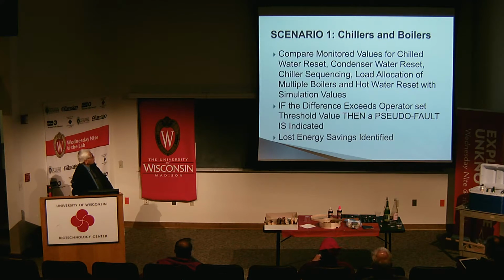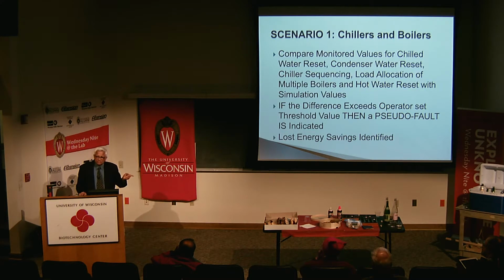Now, chillers and boilers. In this case, the monitored values for chilled water reset, condenser water reset, hot water reset, they are not optimal when you compare with simulation results. They are off. So these again are called pseudo faults, and you identify what is the energy penalty or lost energy savings. These again I consider as pseudo faults because with the set point controller, there is nothing wrong with the temperature sensor.